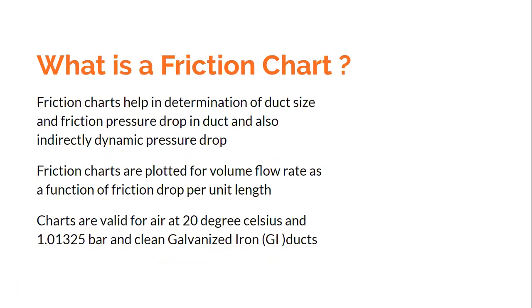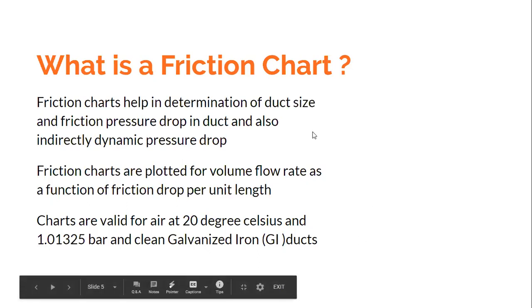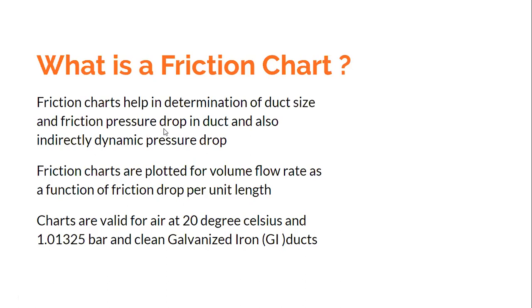So what is a friction chart? A friction chart is similar to other charts you have been using in thermal engineering courses — for example, the Mollier chart or the psychrometric chart. These graphical representations of properties are very handy for practicing engineers. Friction charts are used by practicing engineers to determine the duct sizes and the frictional pressure drop, and can also be used for indirectly determining the dynamic pressure drop.